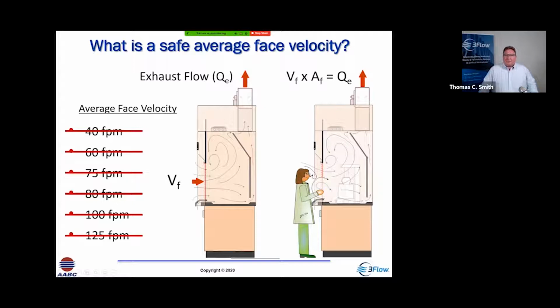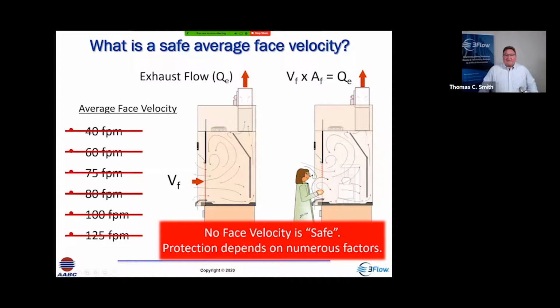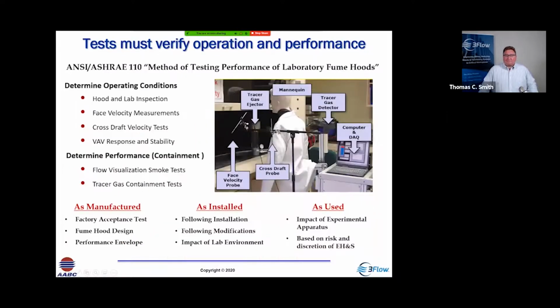And we don't know who's going to be using the hood. We don't know what materials and equipment are being used inside the hood. So how can we arbitrarily pick a face velocity that's going to maintain adequate containment with respect to all the factors that influence performance? So we have to make sure that when the face velocity is specified, we have the appropriate amount of flow to deliver that face velocity, but we can't say it's safe. We can only say it's operating at a particular face velocity. So there is no face velocity that is safe. There are many other factors that influence protection.